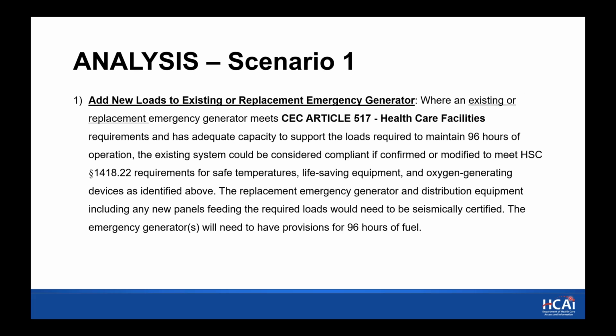Scenario 1, as I said, is adding new loads to the existing or replacement generator. This takes into account where the existing generator meets CEC Article 517 healthcare facility requirements and has adequate capacity to support the additional loads required to maintain 96 hours of operation for temperature controlled life-saving equipment and oxygen generating devices. Typically we would see these existing generators on site. If the capacity is there, that would be a great solution. You still are going to need to satisfy the requirements for 96 hours of fuel in that scenario.